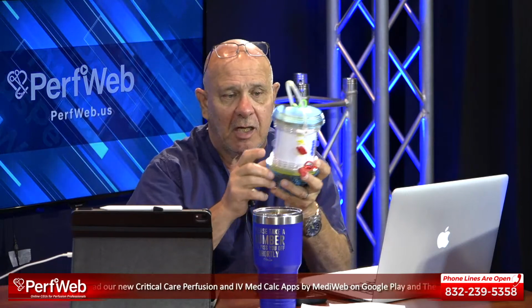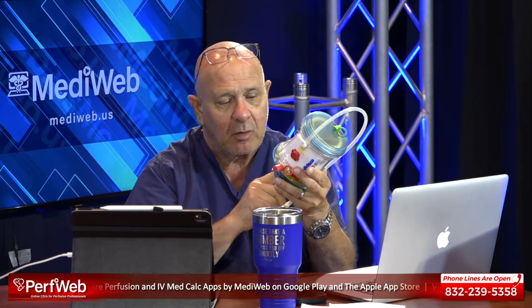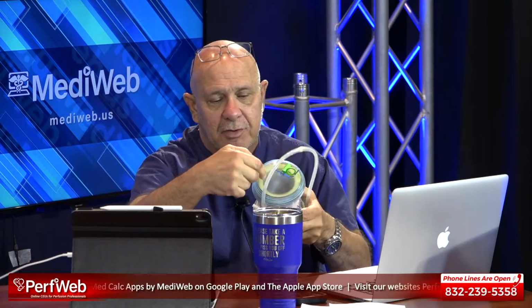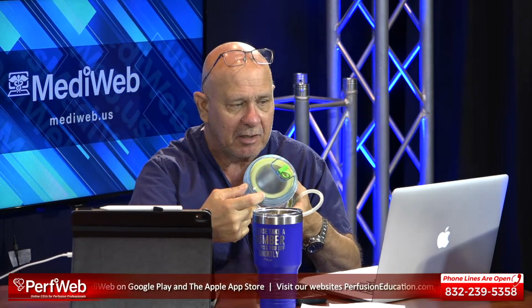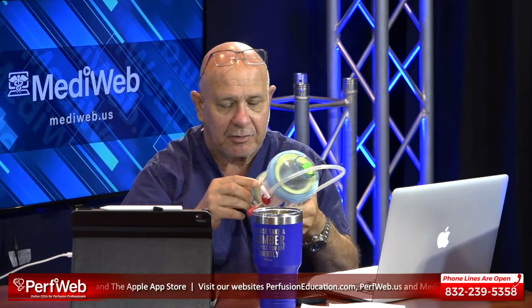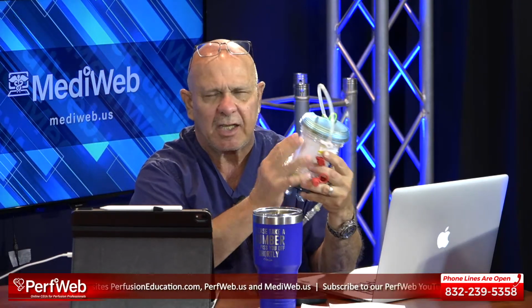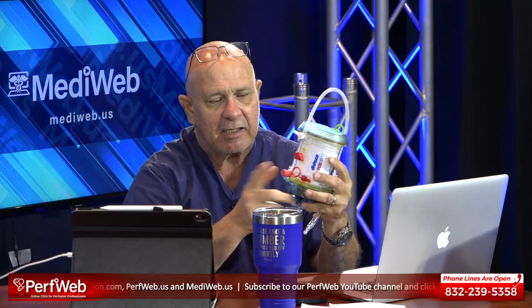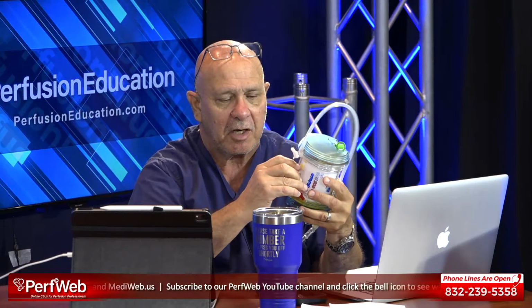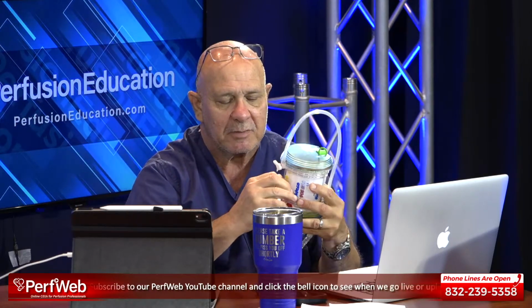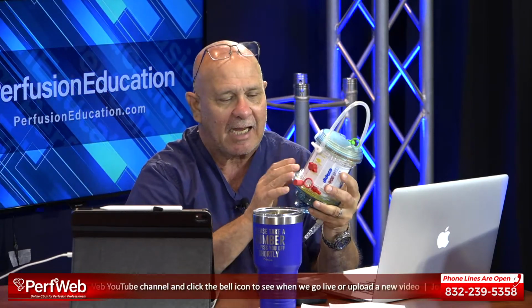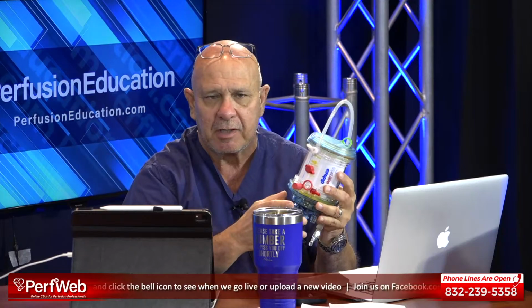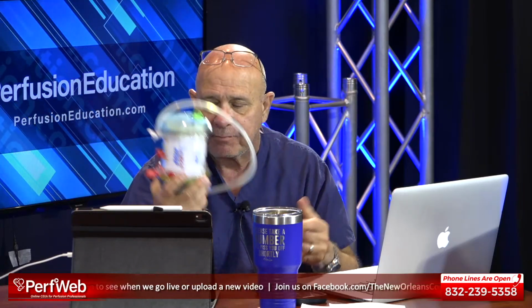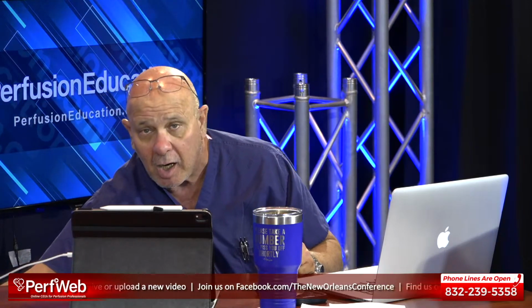So very durable things, and the fibers are, of course, all inside. This is also reverse flow. The gas comes in, goes through, you see the pot right there. I don't know if you can see it or not. You can see it's potted, and the gas goes through there, exits the gas outlet port. Blood comes in here through the heat exchanger, goes on the outside through the fiber bundle, and then comes out here arterialized. And you have a place here for cardioplegia. We only use these for ECMO. This is probably just a leftover housing design, because generally speaking, you're not going to need this if you're on ECMO. But I guess you could use it for something. But that's an oxygenator, and they're very hard.